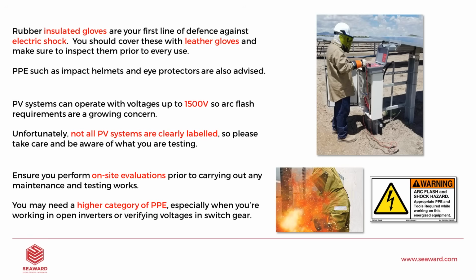And we should also ensure that we perform an on-site evaluation with regard to safety before we begin works. Don't just go there, open up the combiner, connect, and push the auto button to test. Okay, we really should be prepared. And it alarms me sometimes, the people that I work with who are not so aware of the dangers they face when working inside the combiner box. And if you have any fears at all, it's probably best not to work in the combiner and work at the string level if you can.